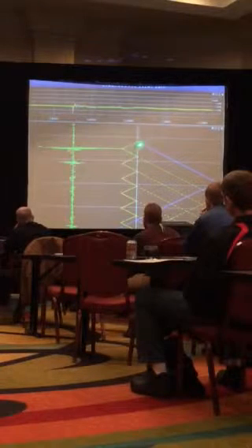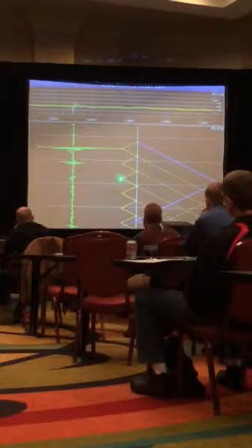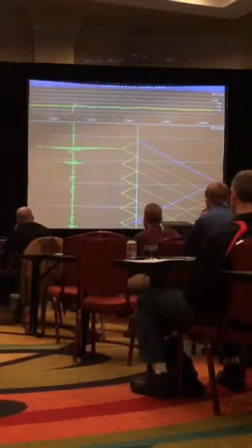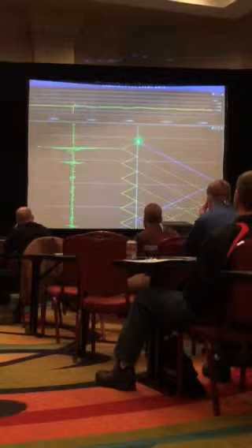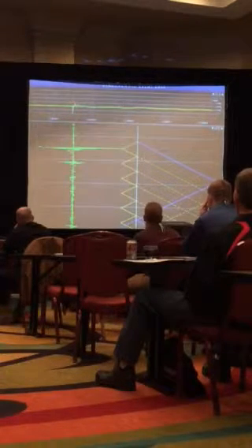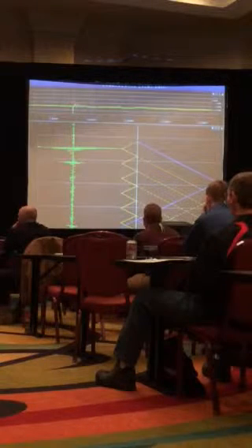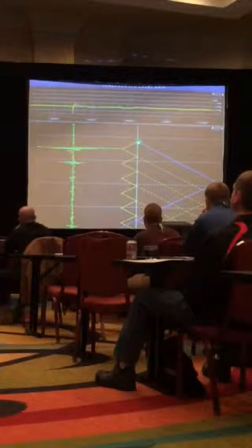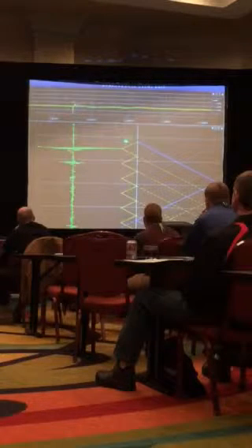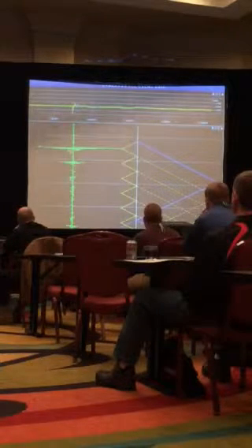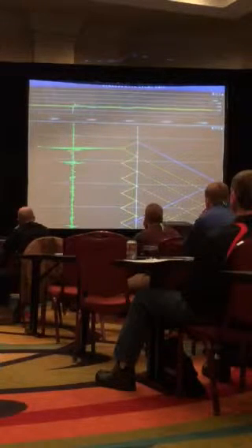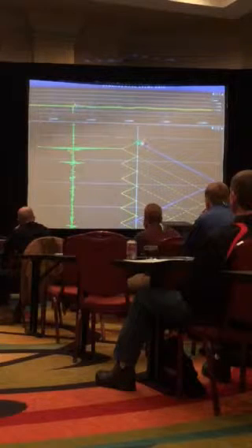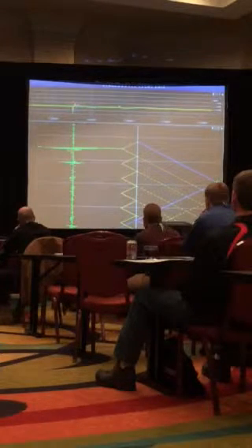So what's so cool is we can start to use these observations of these blips to tell us how far the fault is. Another thing that's interesting is this is where the fault occurred, right where the green dot is. So that's when the fault occurs. I don't know anything about it until this much time has passed. It's already old news by the time it gets to me. Not quite yesterday's news, or cold mashed potatoes, but it's old. And it's even older when it gets to you because the fault happened to be closer to me.